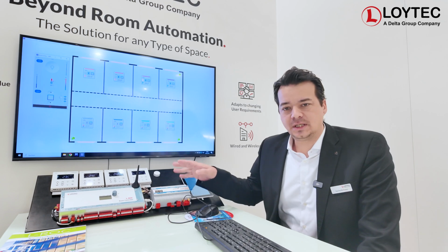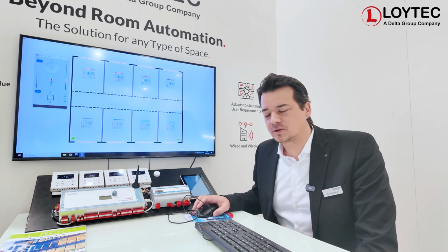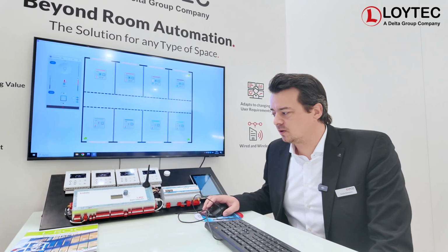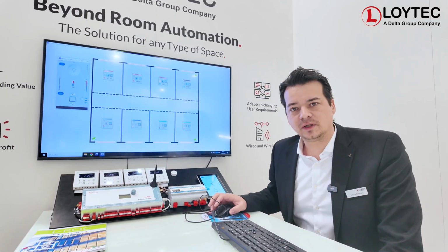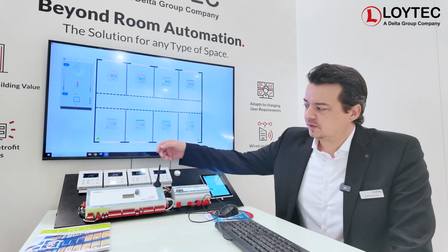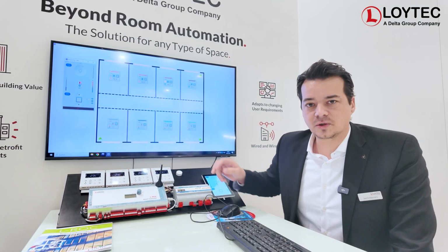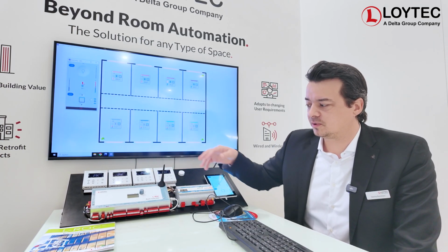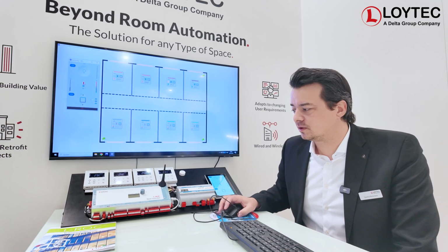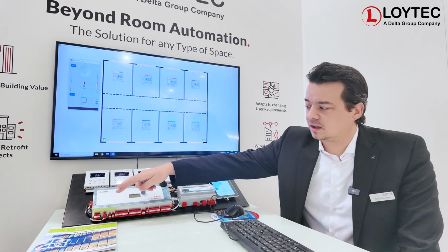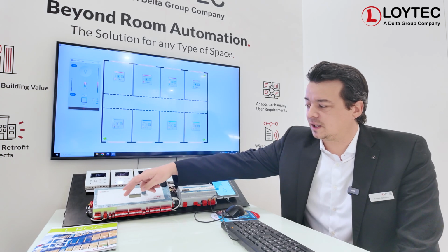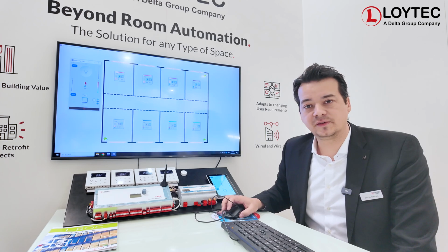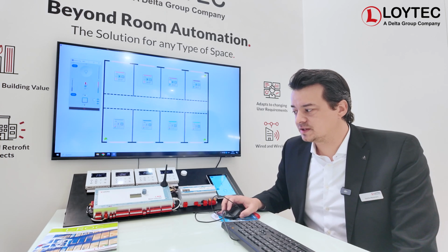So the setup that you see here shows our LROC 400 room controller, and it is capable of many different protocols. It has all the standard interfaces that you will need. So we have at the top relays to control sunblinds up and down via relays. We have triac outputs, we have 0 to 10 volt outputs, different inputs for window contacts or dew point sensors. We have an SMI channel to control the blinds via SMI, and we have a DALI port for connecting to the lighting system, lamps as well as multi-sensors.